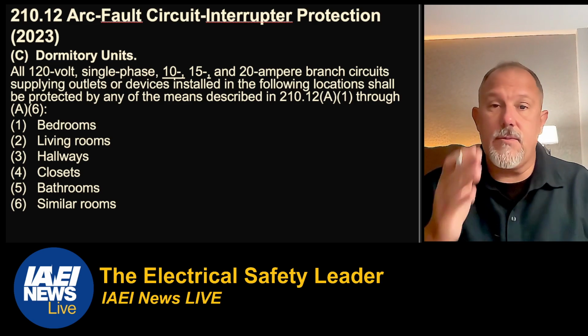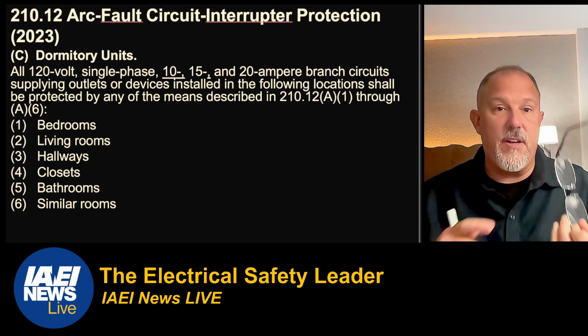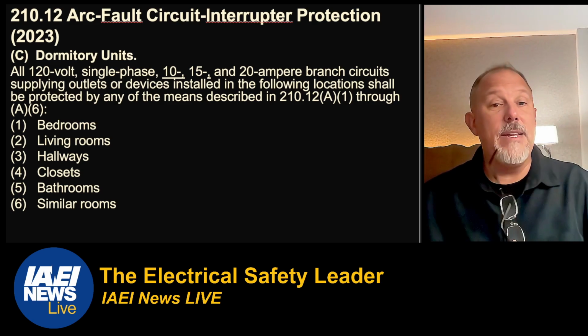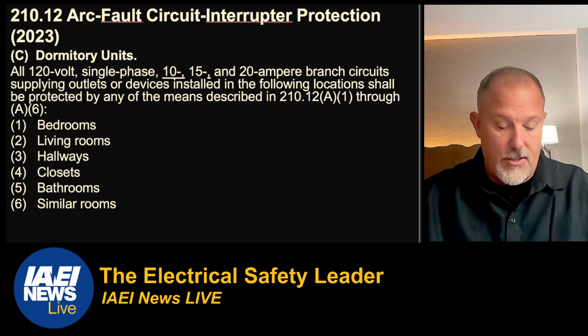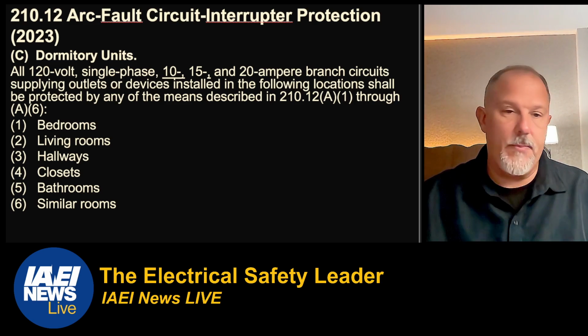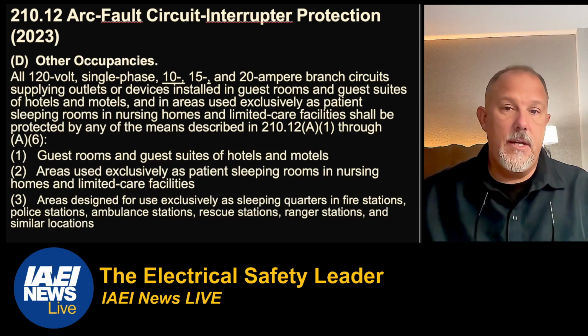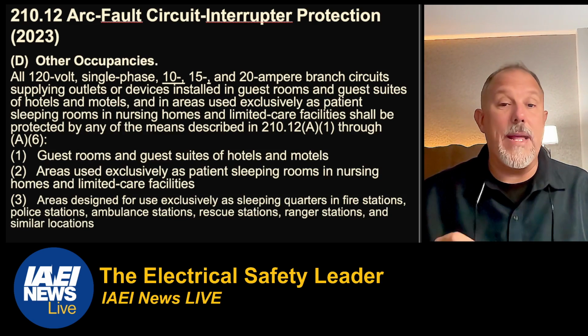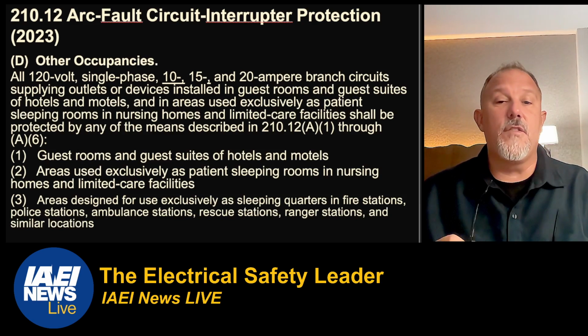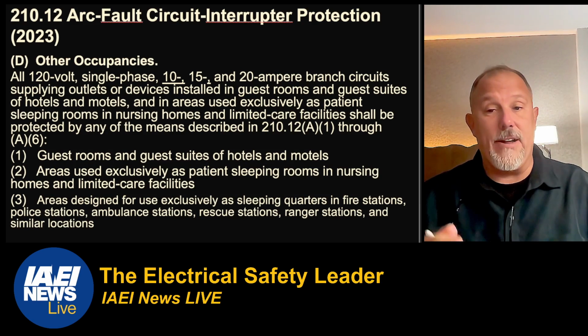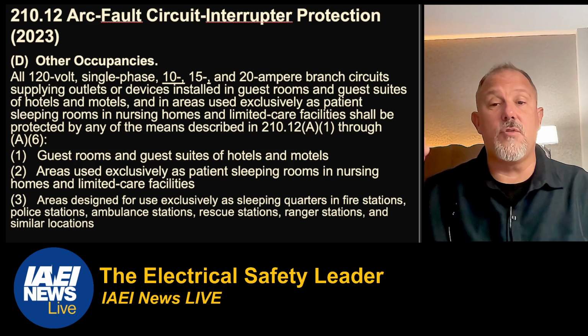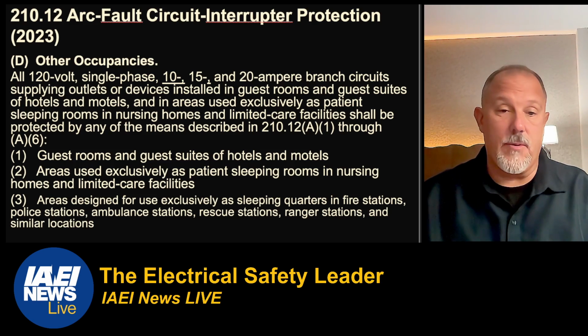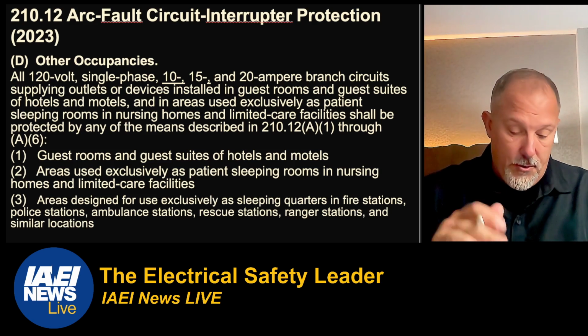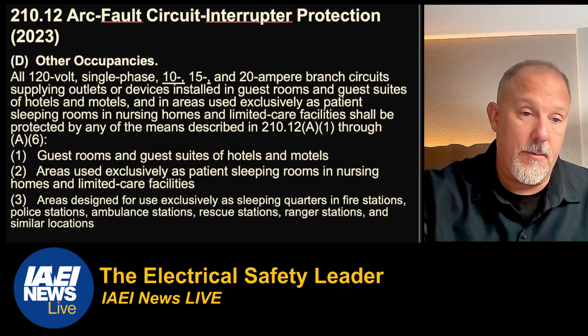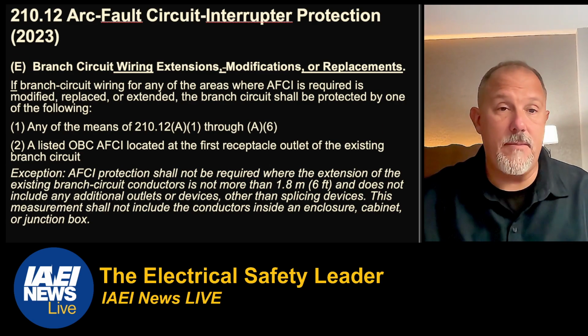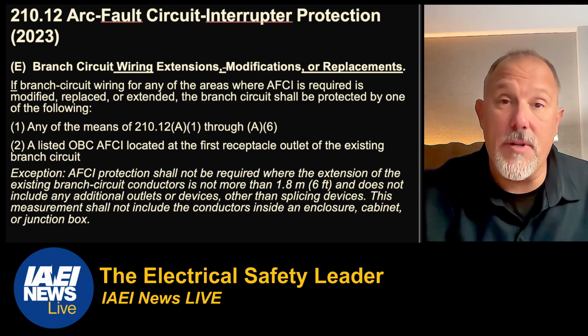So in dormitory units, we've got the 10 amp AFCI, and then we add these 6 rooms. So you have bedrooms, living rooms, hallways, closets, bathrooms, and similar rooms. And that has not changed. That was the same as it was. We just added it into a list format. Now you've got your other occupancies. What we added here was areas designed for use exclusively as sleeping quarters in fire stations, police stations, ambulance stations, rescue stations, ranger stations, and similar locations. So that is a new requirement for the 2023 code. Not a dwelling unit, but I just threw it in there because it's a bonus question.